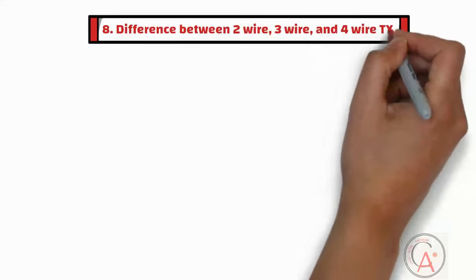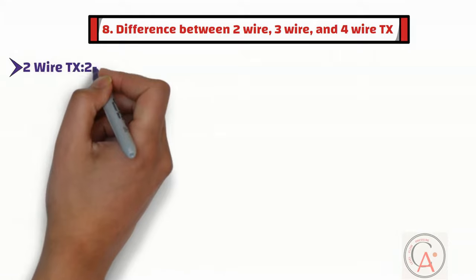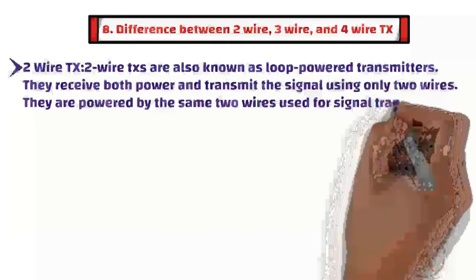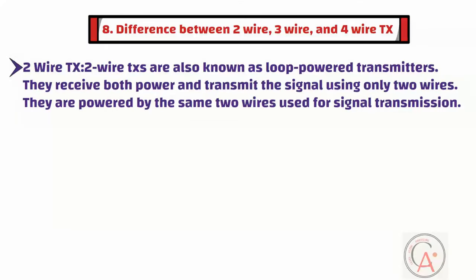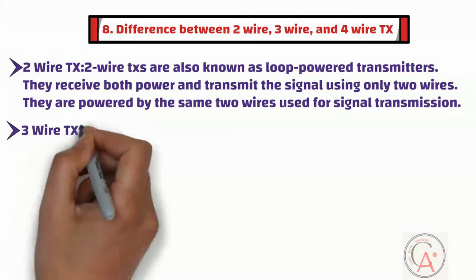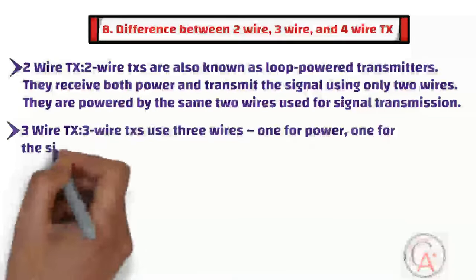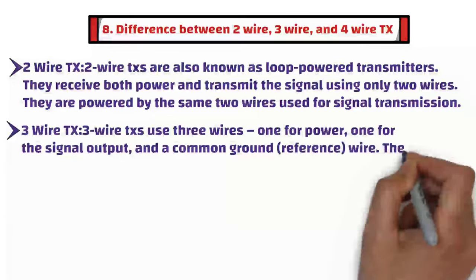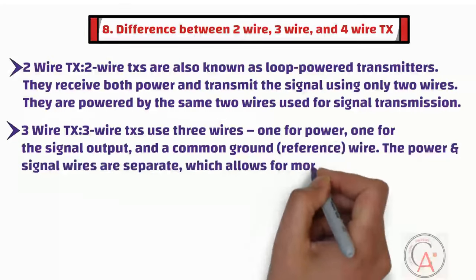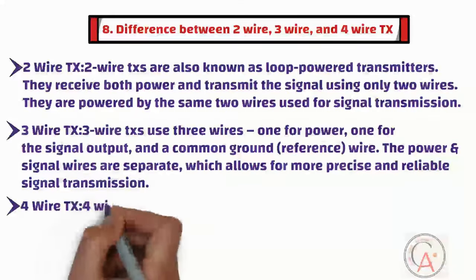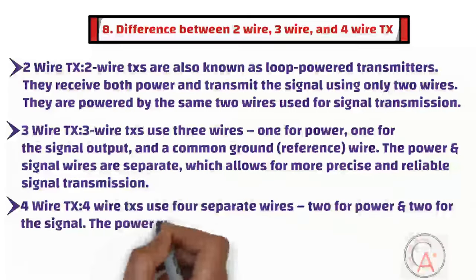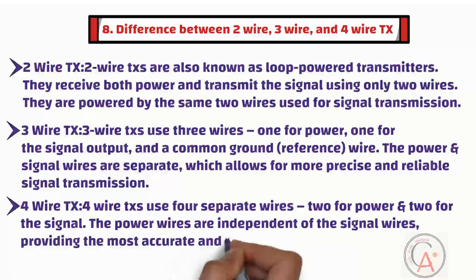The eighth question is: what is the difference between two-wire, three-wire, and four-wire transmitters? Two-wire transmitters, also known as loop-powered transmitters, receive both power and transmit the signal using only two wires. Three-wire transmitters use three wires — one for power, one for the signal output, and a common ground or reference wire, allowing for more precise and reliable signal transmission. Four-wire transmitters use four separate wires — two for power and two for the signal — providing the most accurate and reliable measurements.